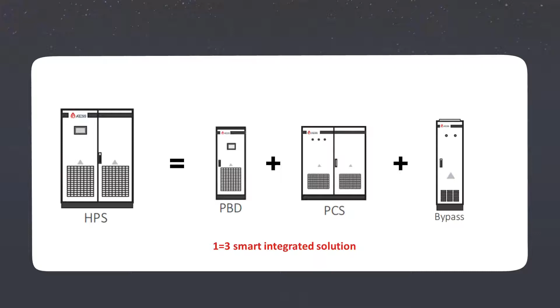The following product is an accessory for HPS, because we know that HPS has only one AC input. So when the project has both the grid and the generator, we will use this product, ATS. The full name is Automatic Transfer Switch. It allows the grid and the generator to be connected to the system at the same time, and recognizes who is connected to the system. It also communicates with HPS to tell the HPS whether the grid or the generator is connected to the system, so that the HPS can realize the transfer switch between grid mode and generator mode.